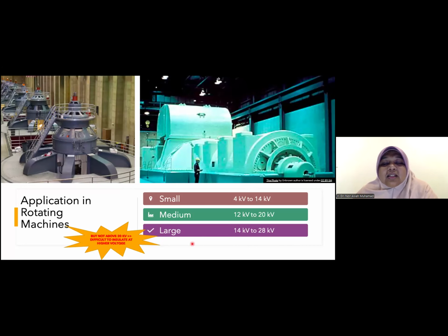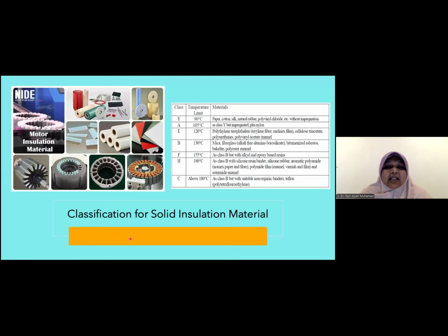Because with a large machine, the insulation becomes bigger than the machine because of the very high current in the system, so it will be more costly. That's why generation of more than 20 kV is difficult to insulate. So the rotating machine has two parts, a stationary part and a rotating part. Then for this machine, the insulation materials are classified into seven classes.